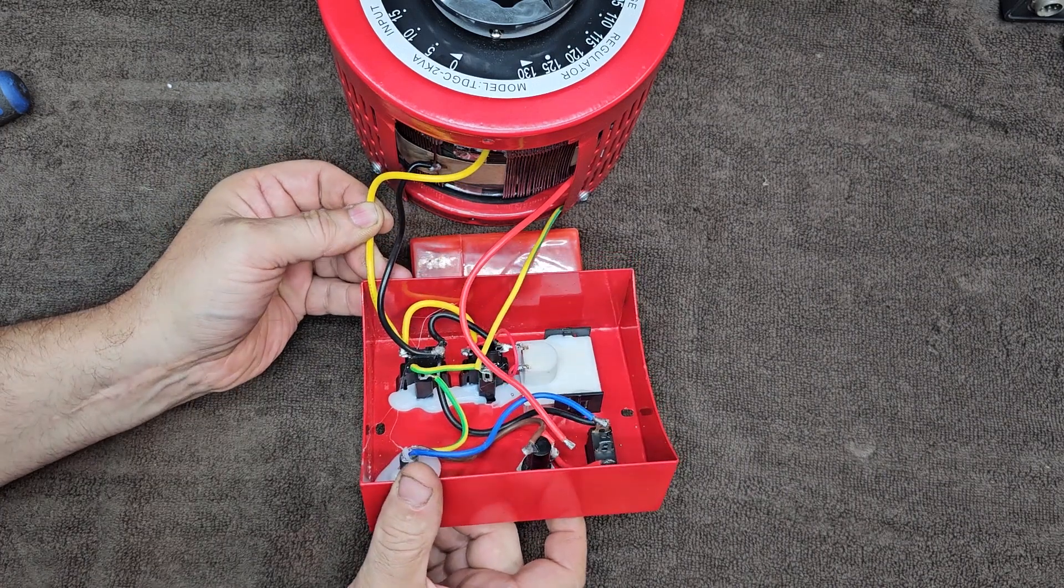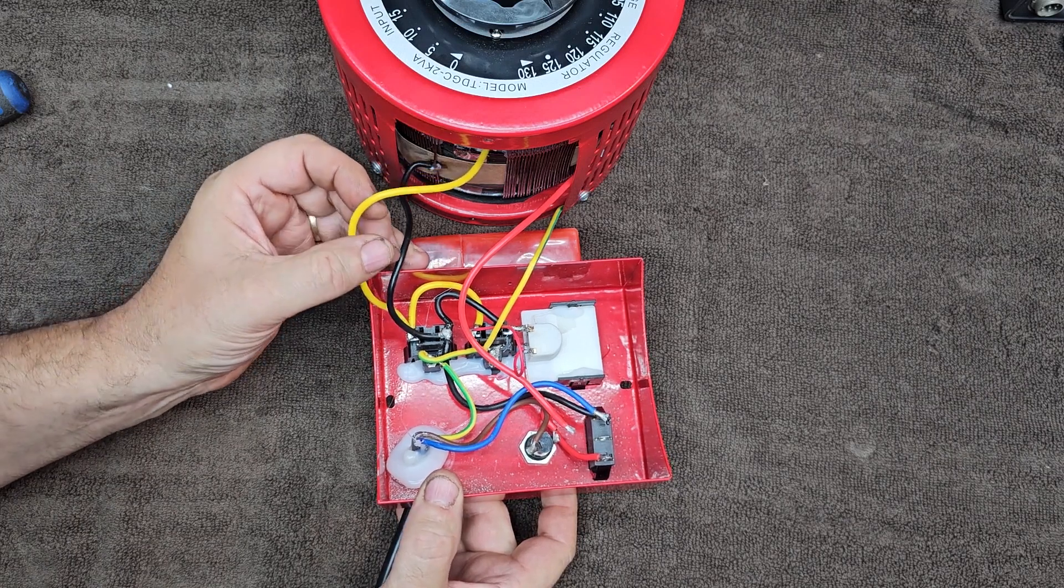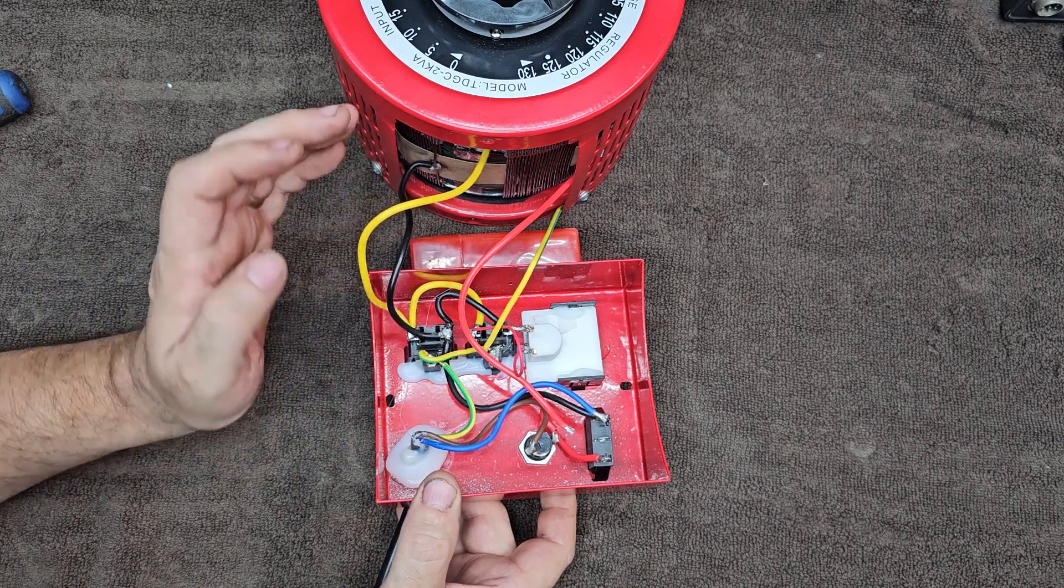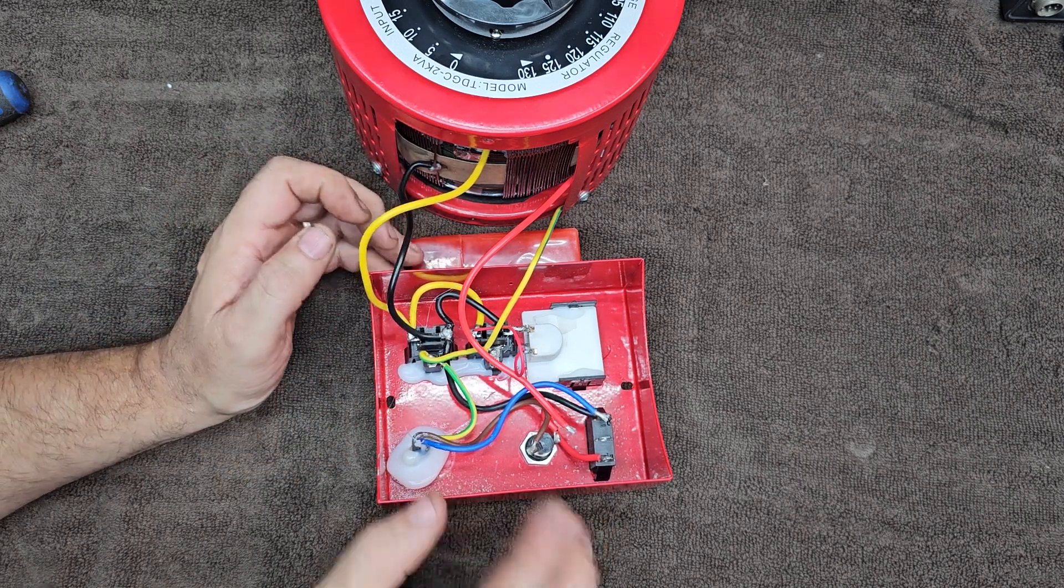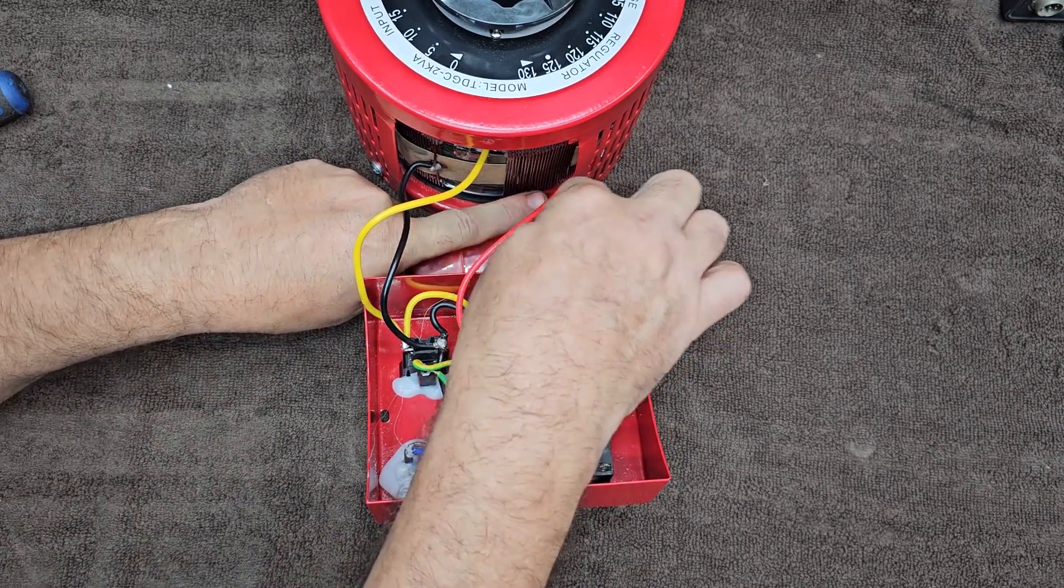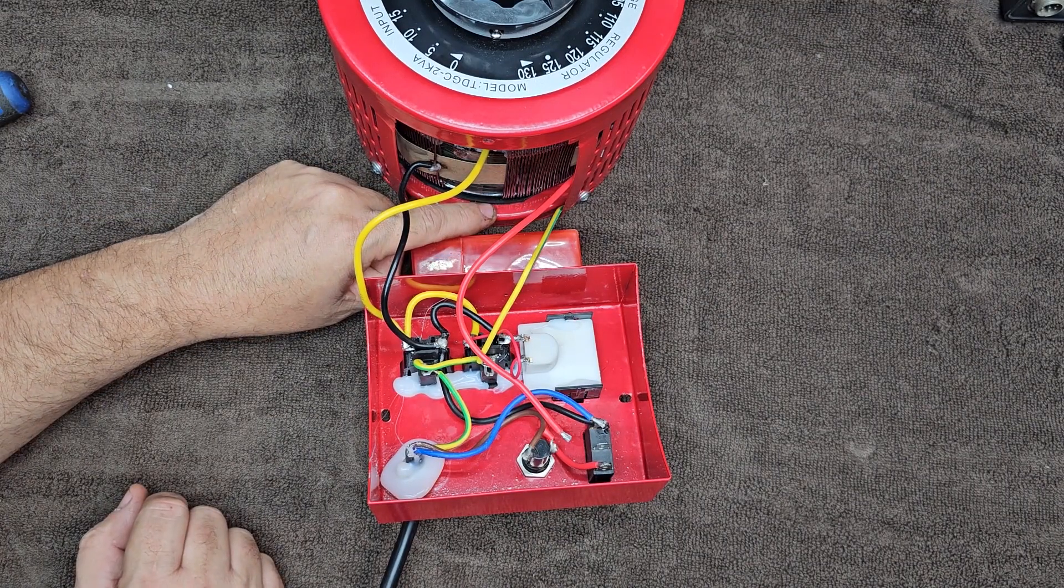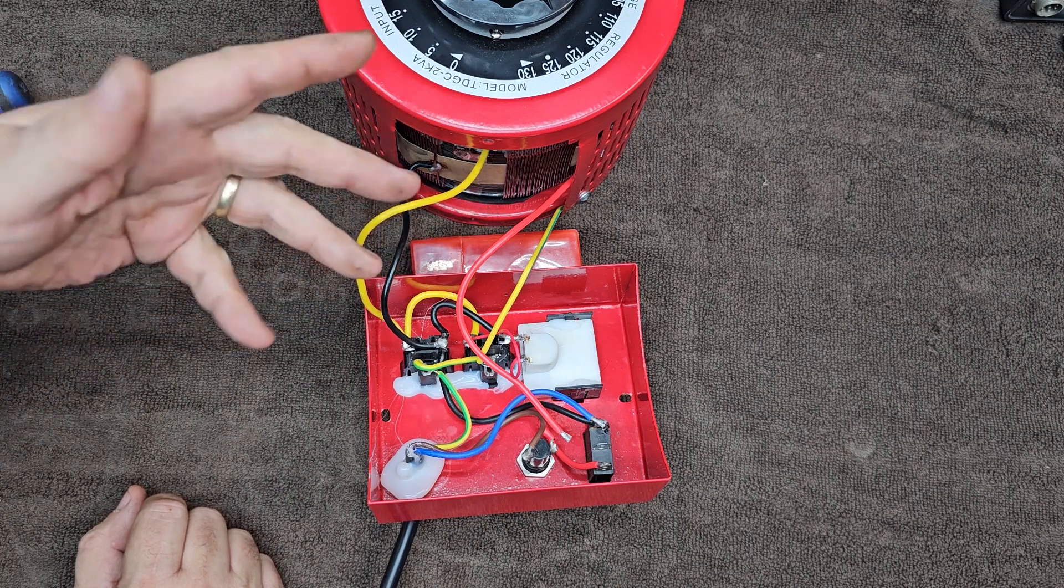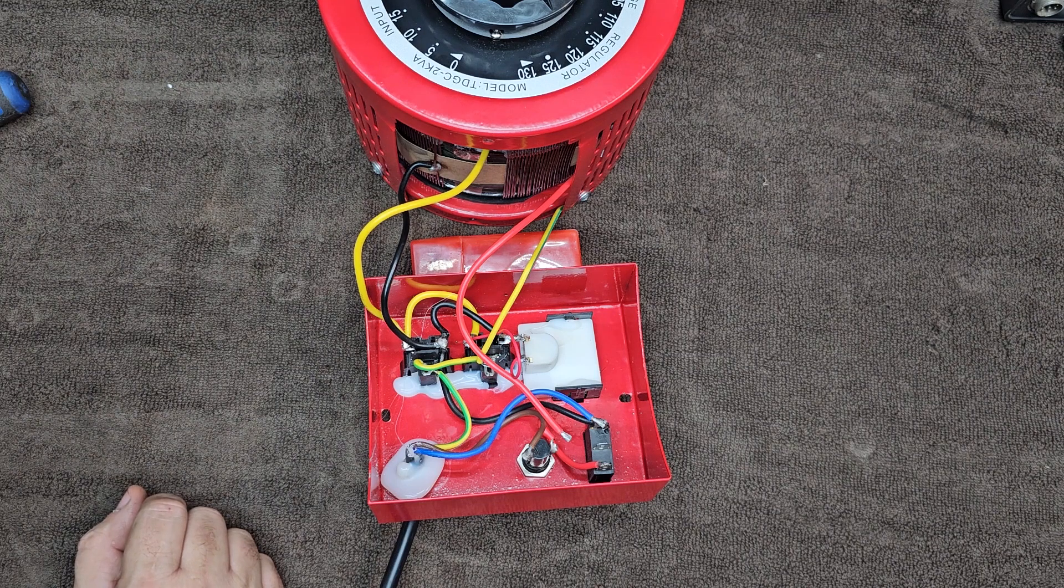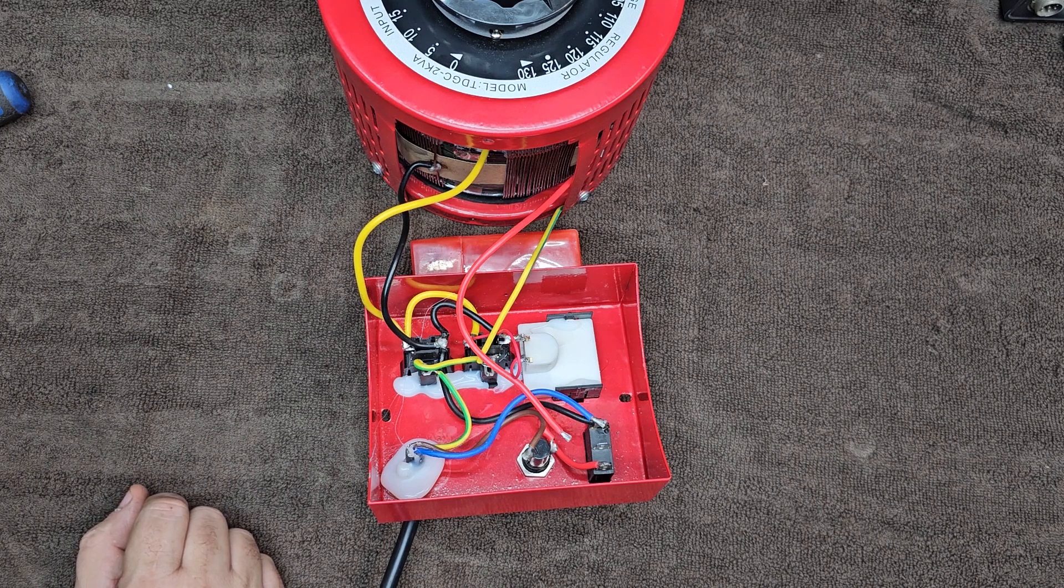I'll have to find out whether it's 10 or 12 or 14 gauge wire but the wiring doesn't look so bad. But again bearing in mind the ground which is this one here, they've pinched it off behind a screw in the side there and they've not removed the paint or done anything to properly ground it. So that has to be dealt with and as well as getting this top part properly grounded.